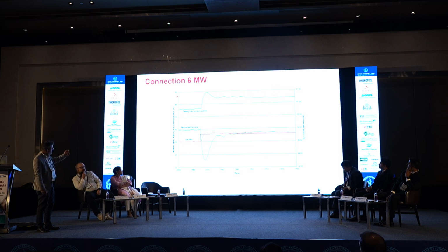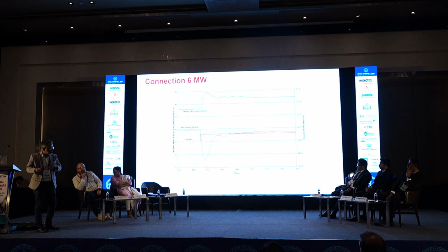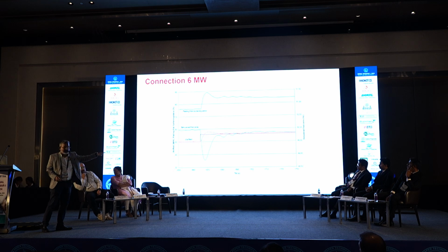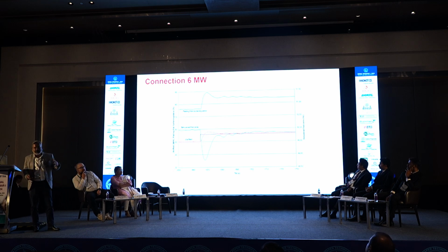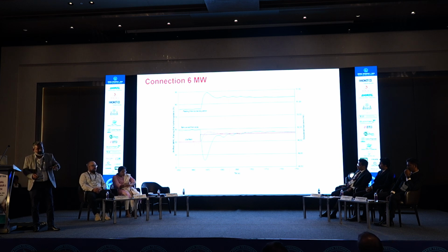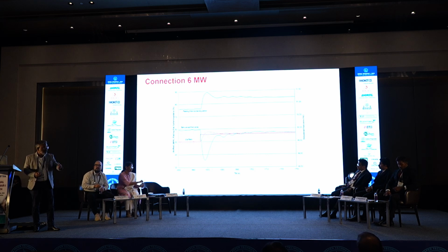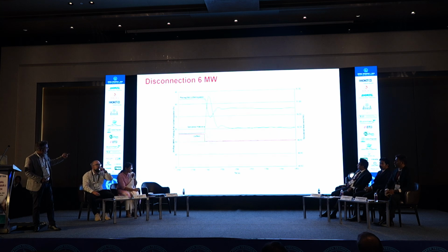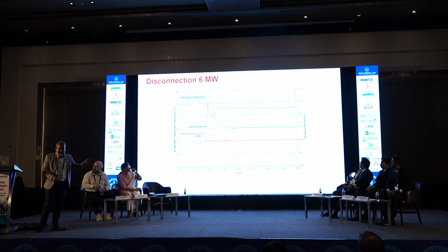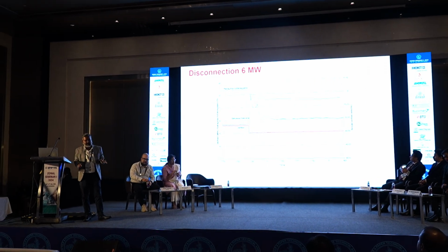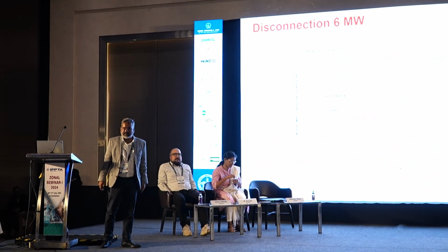So immediately the simulated frequency went down, and the turbine controller gave its output to increase the actual power of the machine. Once the actual power of the machine is increased, the islanded frequency gets stabilized. So this is what we make sure, that in an island, the frequency gets stabilized even with the connection and disconnection of the loads, and we see how much load swing the system can handle. For this case, connection of 6 megawatt as well as disconnection of 6 megawatt is quite possible, and the system gets stabilized. Beyond that, the system could not handle.